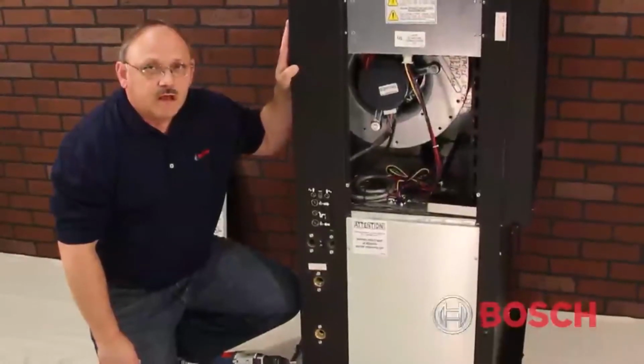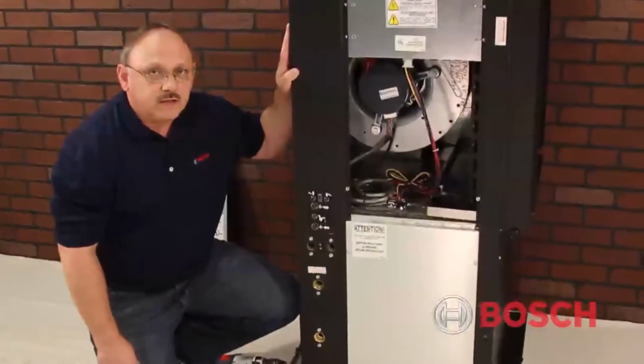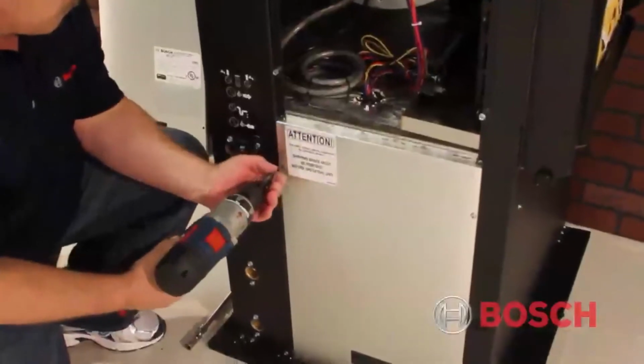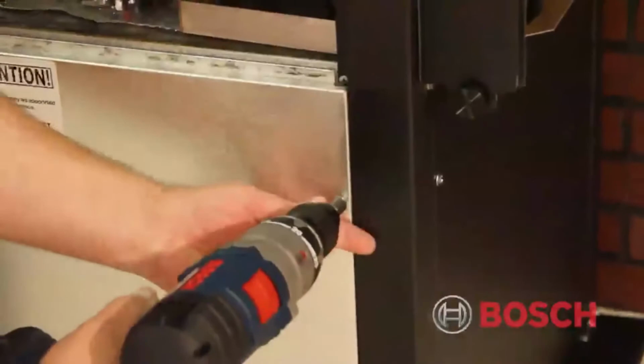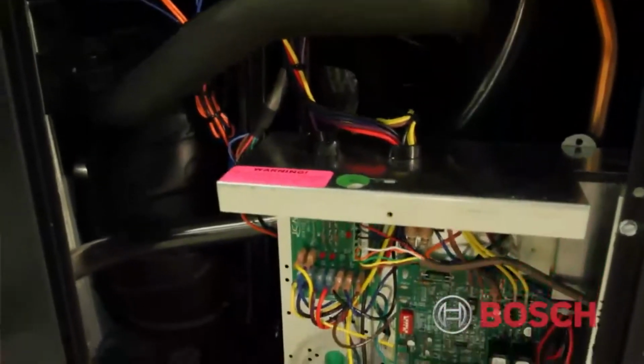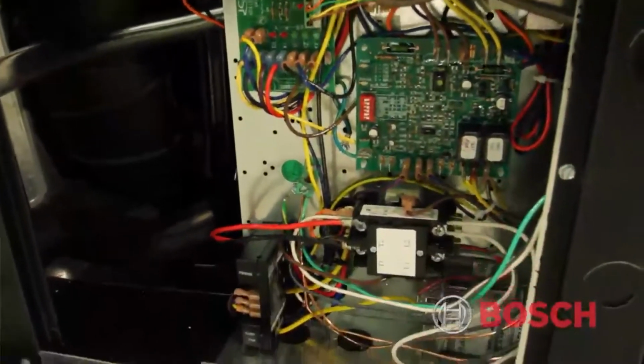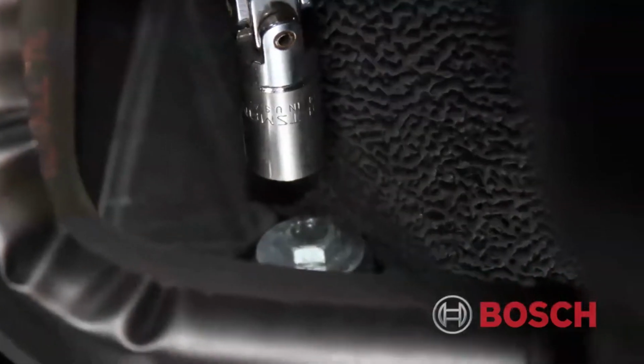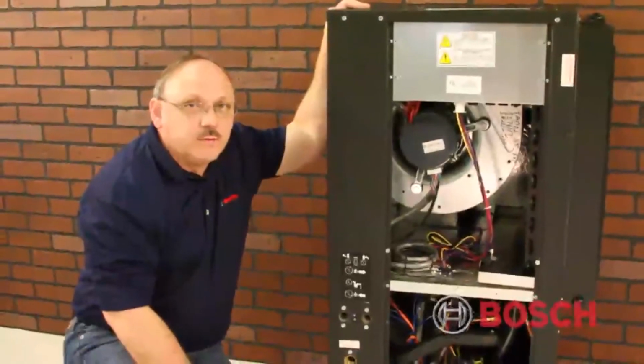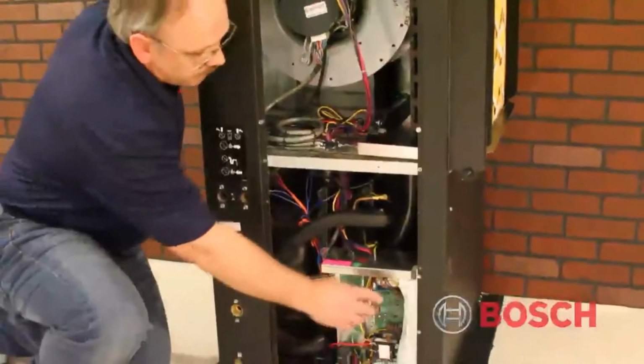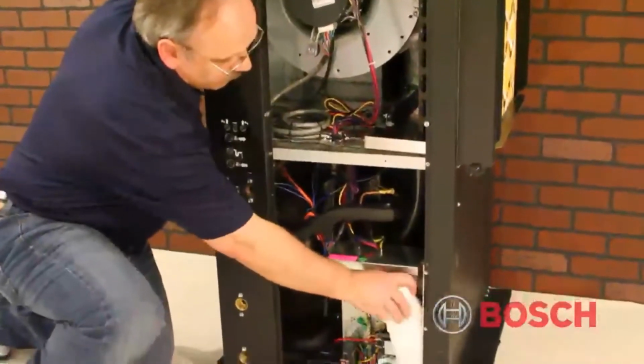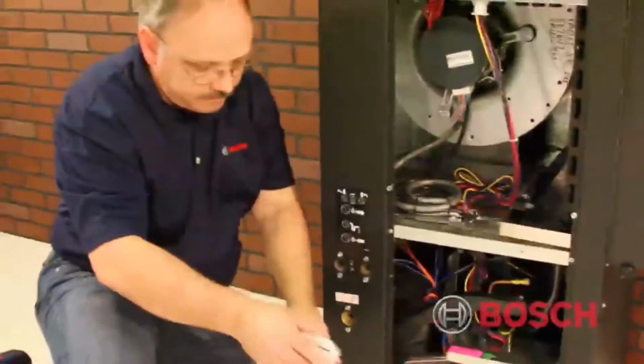Once the shipping block has been removed from the blower assembly, you can now take the lower access panel off of the equipment to give you access to the electrical and mechanical part of the equipment, so that we can now loosen the compressor mounting bolts that have been tightened down prior to shipping. Next thing we're going to do is remove the installation instructions from the electrical box. Every step of the installation instructions should be followed throughout the installation process.